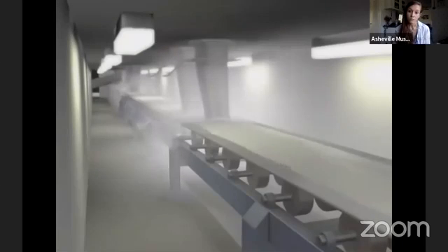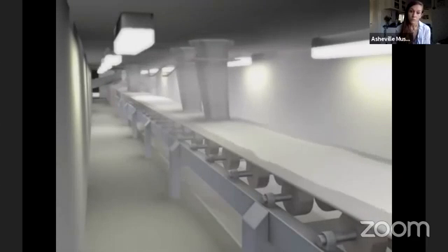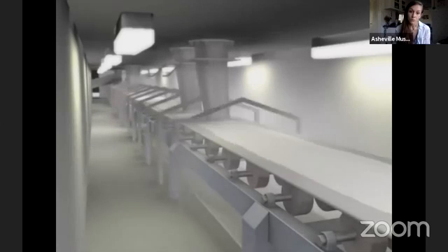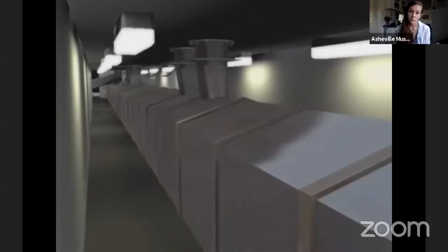But the tunnel was large and ventilated, so this airborne dust did not build up to explosive concentrations. However, in 2007, the company enclosed the conveyor belt with stainless steel panels to protect the sugar from possible contamination. The enclosure was not equipped with a dust collection system.